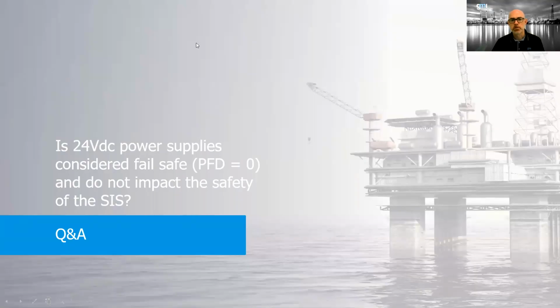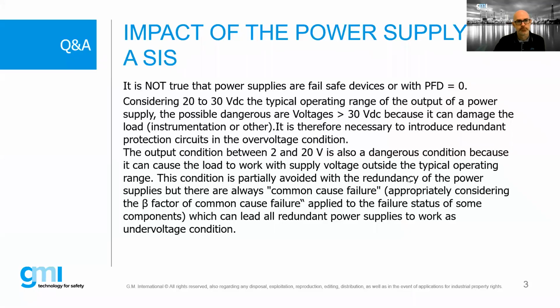Are 24-volt DC power supplies considered fail-safe with PFD equal to 0, so that they do not impact the safety of the SIF? Okay, so it is a very important point because, of course, it is not true that all power supplies are fail-safe devices with a PFD equal to 0.